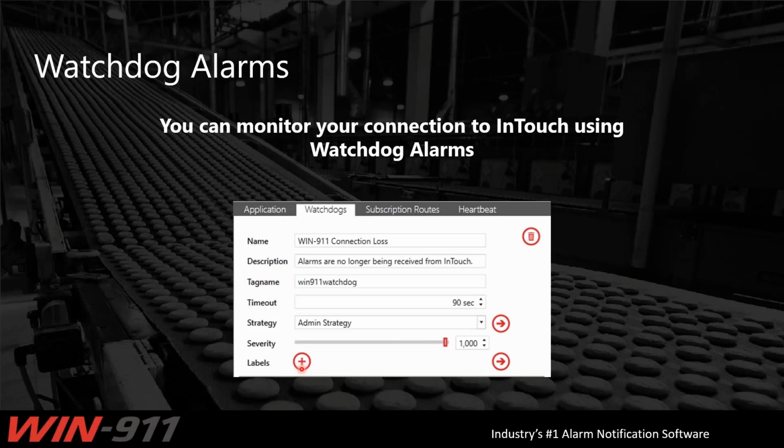One thing we can do is create a watchdog. A watchdog is a way for us to monitor your SCADA. So best practice there is you would have an actual tag that's got to be an alarm, but you could make it a fake alarm, I suppose. One that basically goes active, inactive every 10 seconds. And if we did not see that state change happen within 90 seconds, then we would assume something's wrong with the SCADA, and we would send out our own notification based on what strategy it triggered and what tactic. And so you could decide who gets that call out if that happens.